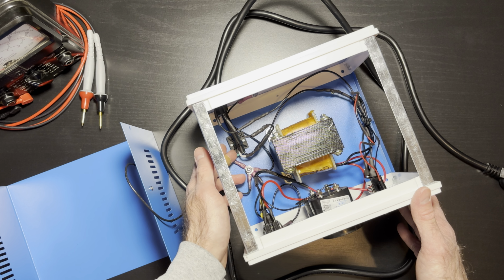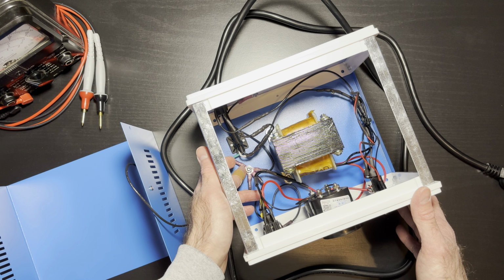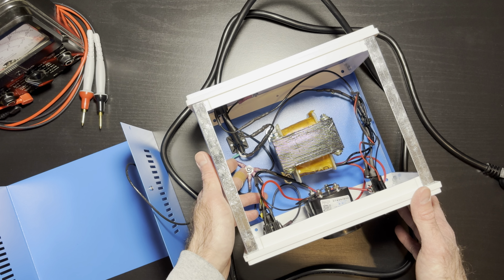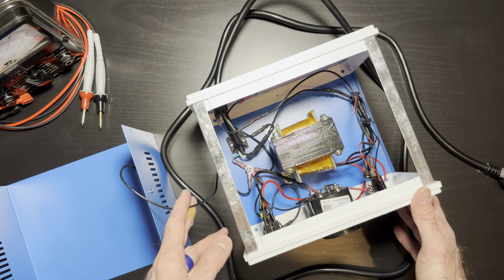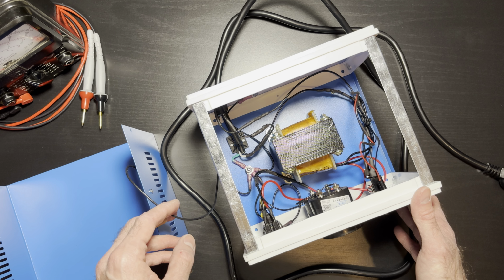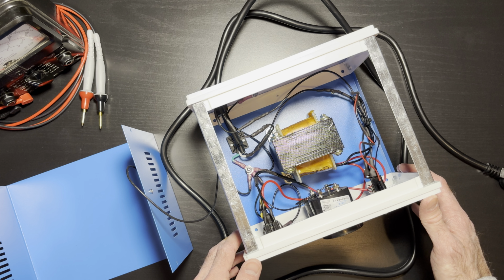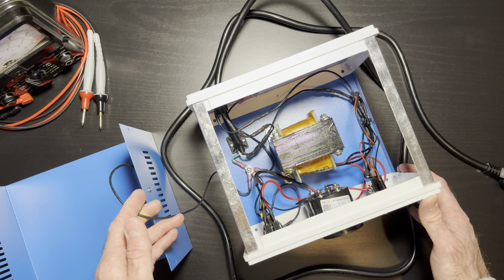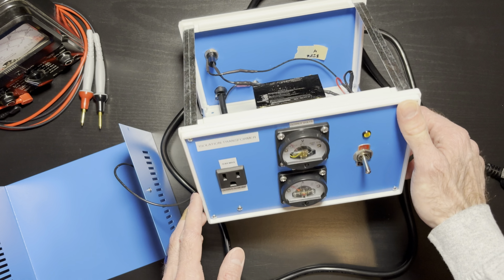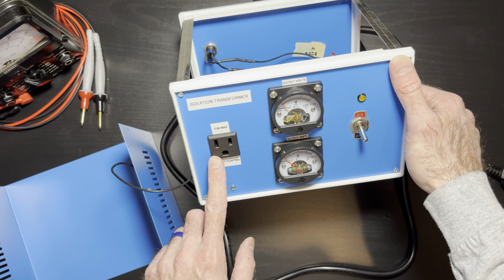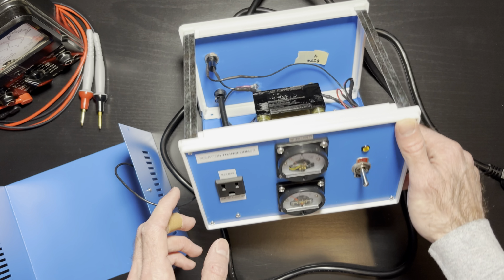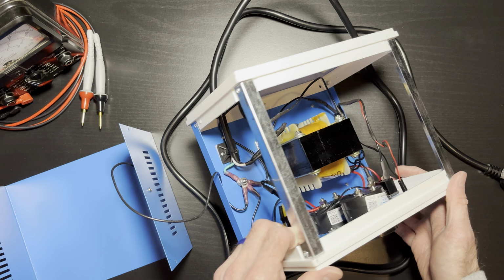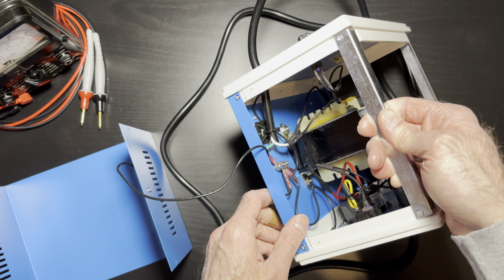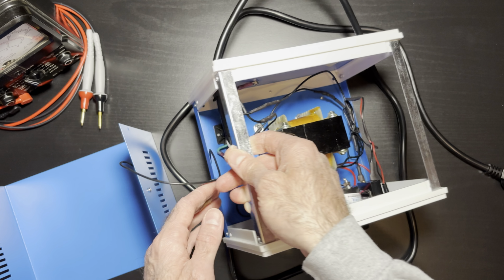And then I did add a ground to the chassis to all the panels. So each panel has its own dedicated 18 gauge ground wire. So if there are any issues, everything's grounded. Obviously with the exception of this outlet here. This is floating, this is just tied off. The actual ground for the receptacle is just tied off, not connected to anything.